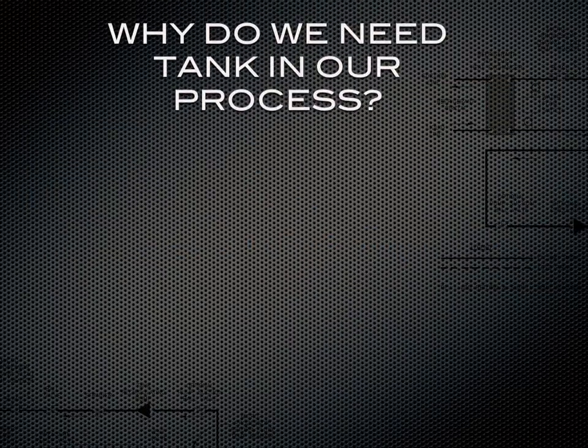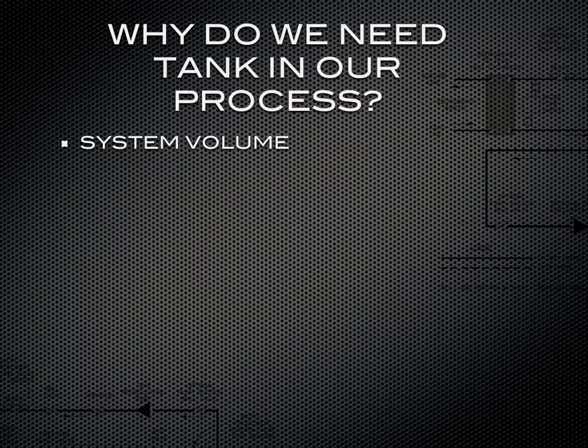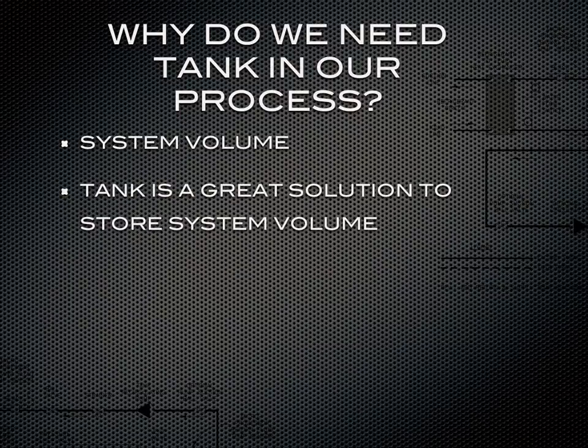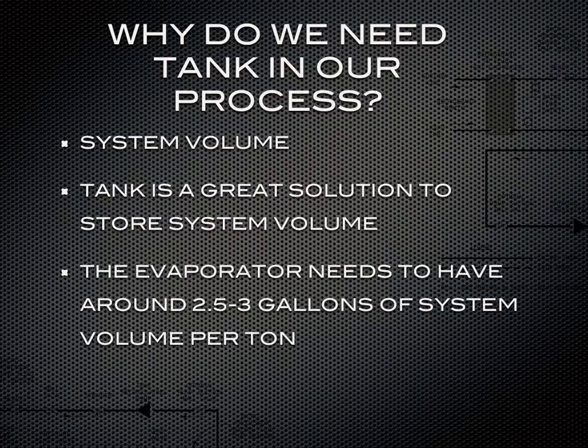Why do we need a tank in our process? One of the main reasons is for system volume. If you don't have enough piping between your chiller and the piece of equipment that you're trying to cool, a tank is a great solution to store that volume. The reason we need system volume is to satisfy the chiller evaporator. The chiller evaporator needs to have around 2.5 to 3 gallons of system volume per ton somewhere in the process. That can be in a tank, that can be in piping, or that can be in both.